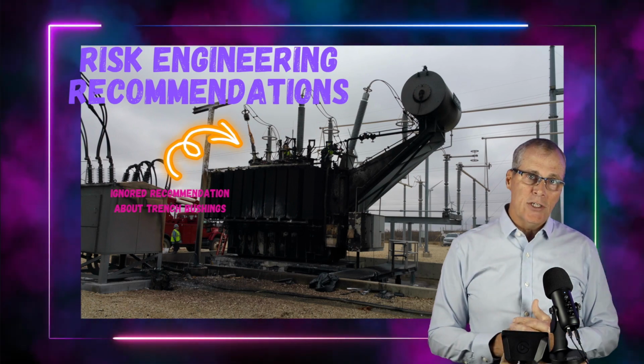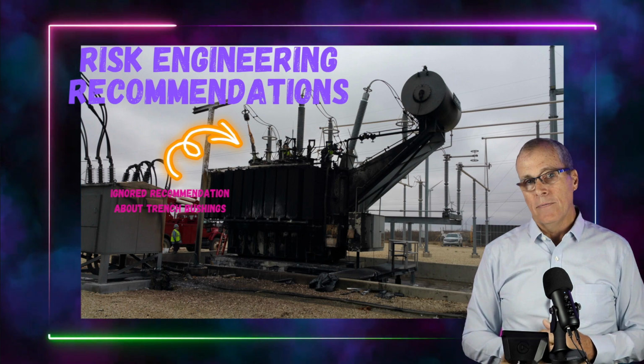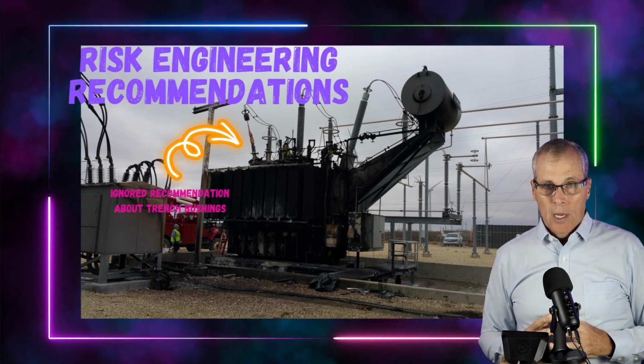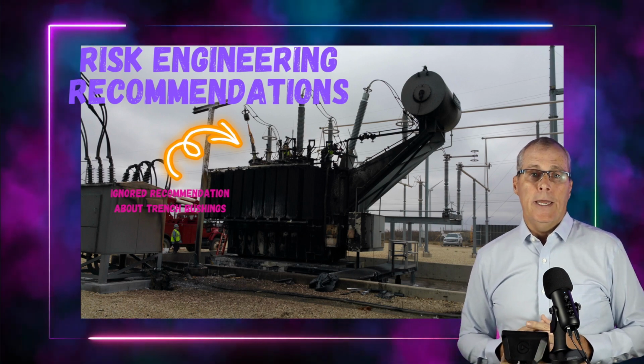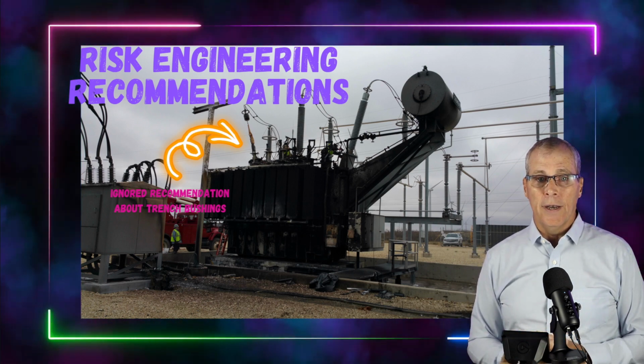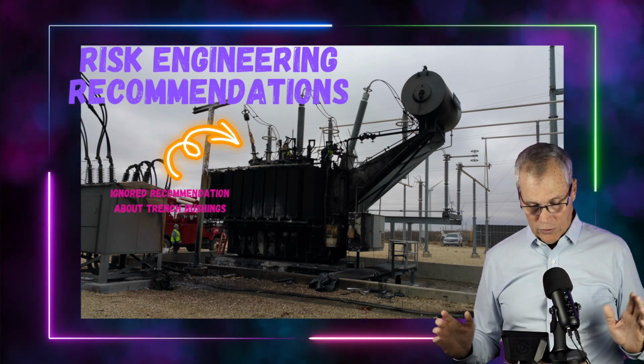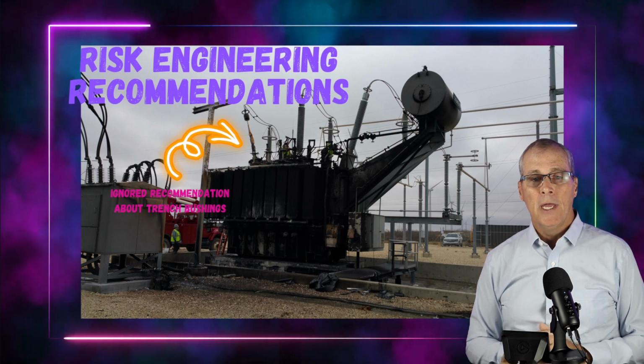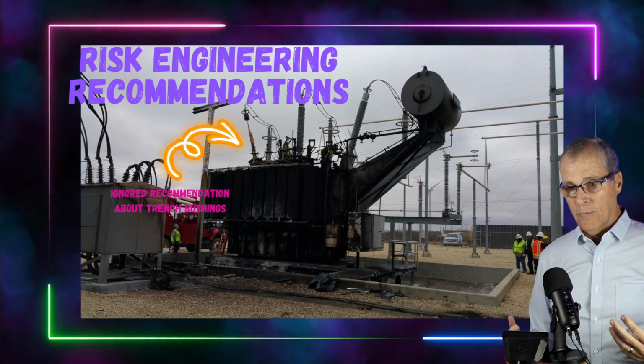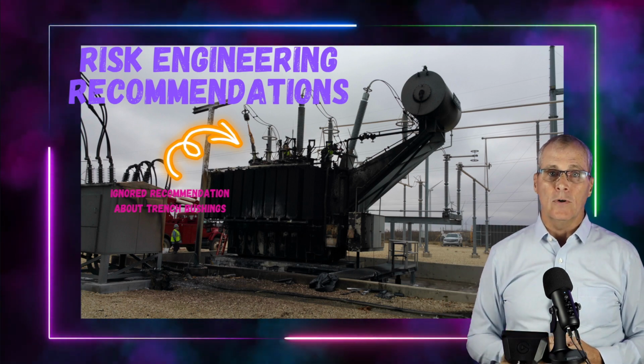Here's a recommendation that basically went ignored. Many of you know about some bushings out there that have a tendency to fail, and it's usually not a matter of if, it's a matter of when. We've seen several of these. Hopefully the industry is done with this issue now, but honestly, what happened, many companies were told, hey, these bushings are failing, and if you don't swap it out, you're going to lose your transformer.